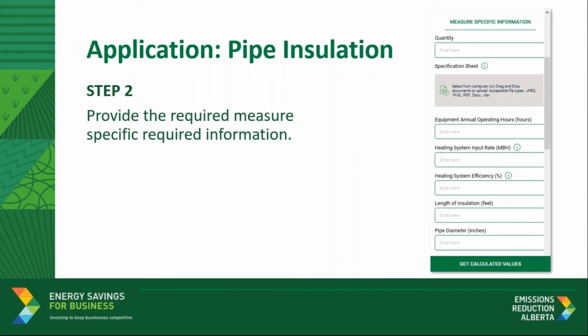The annual equipment operating hours should reflect the uptime of the equipment producing the heat in the pipes being insulated. Similarly, the heating system input rate and heating system efficiency should reflect the capacity of the heat source feeding the pipes being insulated. For applications with multiple pipes being insulated, the length of insulation in feet will need to reflect the average for all pipes, and the same is true for the diameter, although less critical.